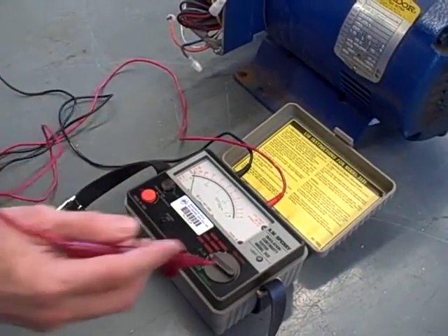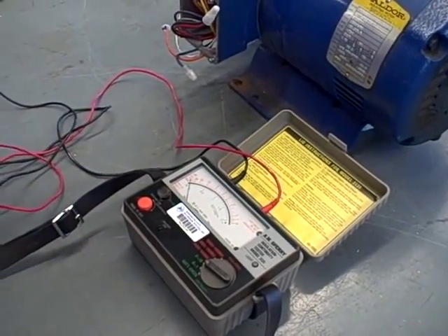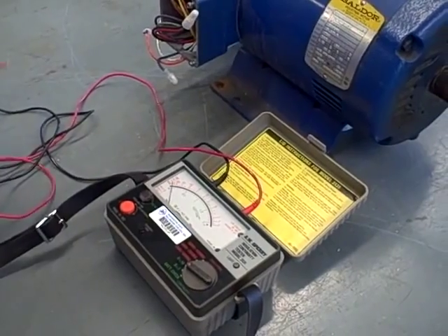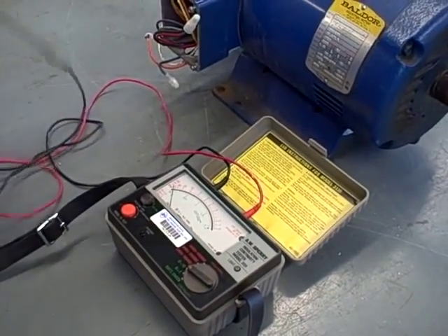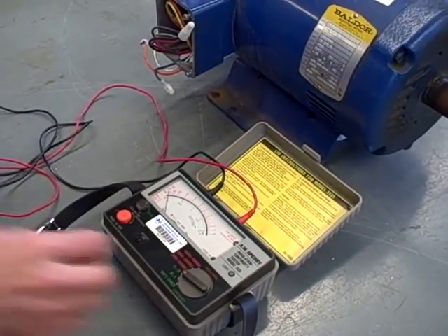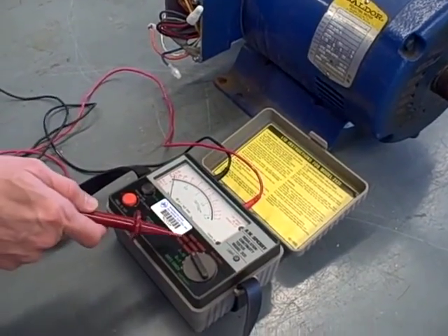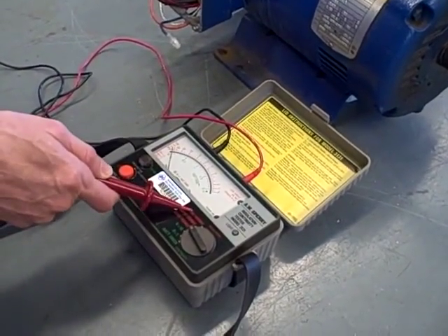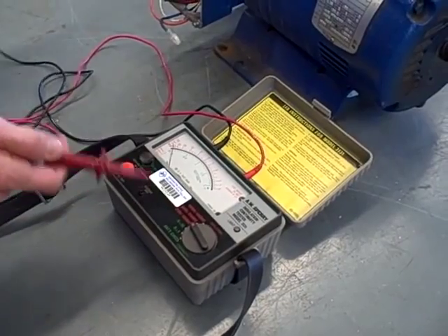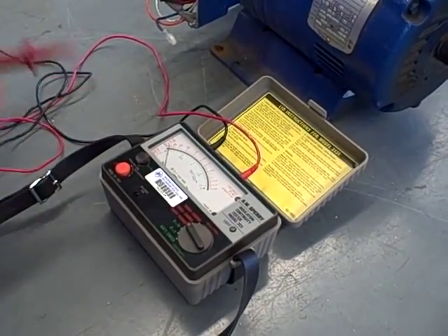We're looking at an insulation tester here, commonly called a Megger. The purpose of this tester is to check for the resistance of the windings of a device like an electric motor using a fairly high voltage. You'll see on these three scales we have a 250 volt, 500 volt, and 1000 volt setting. And we need these high voltages to be able to detect certain types of faults.